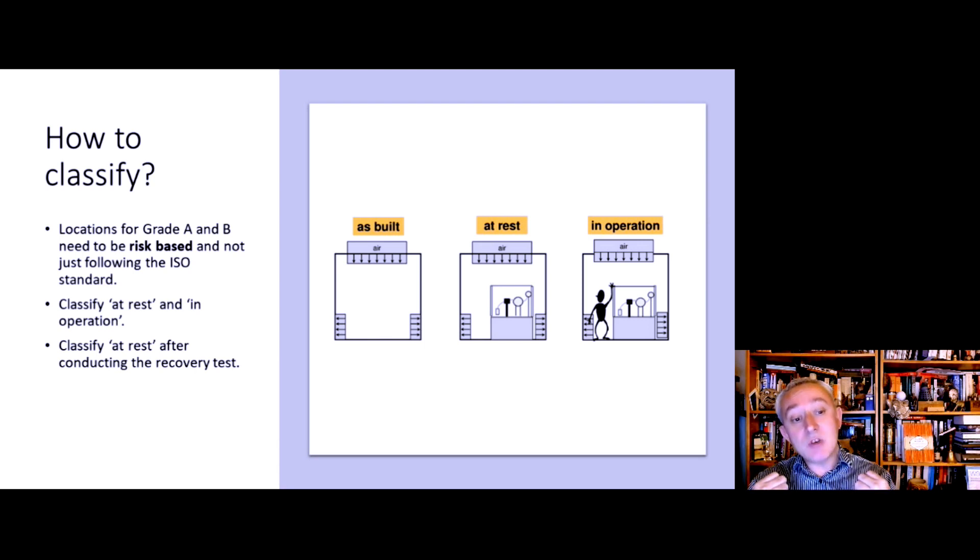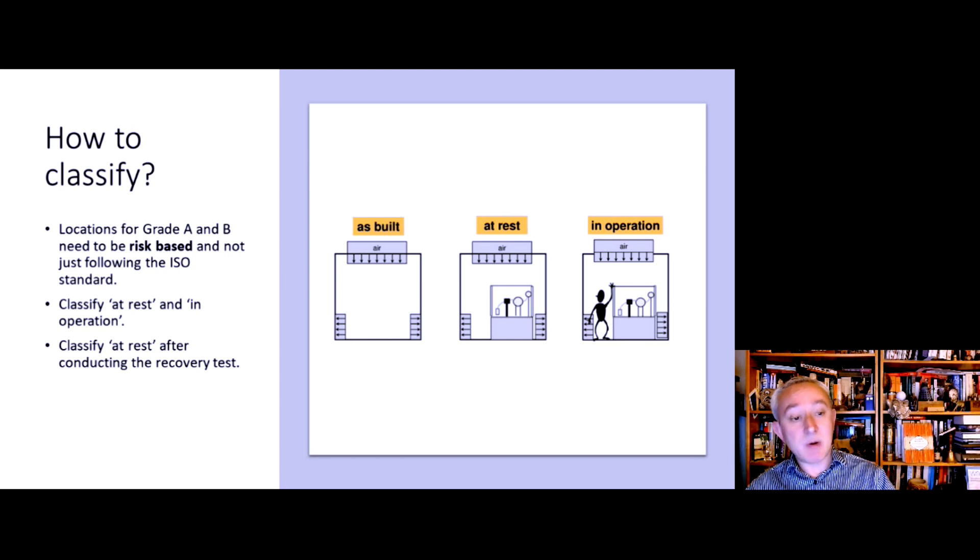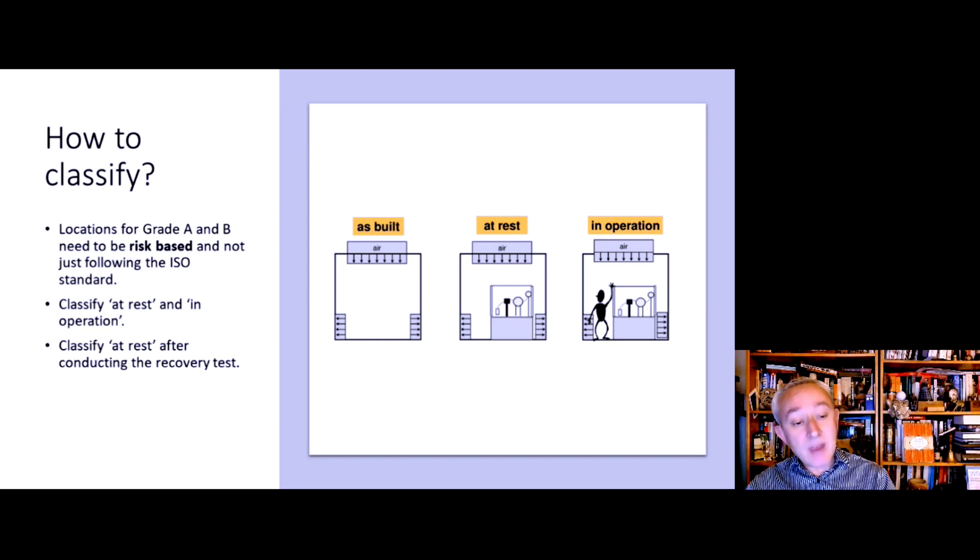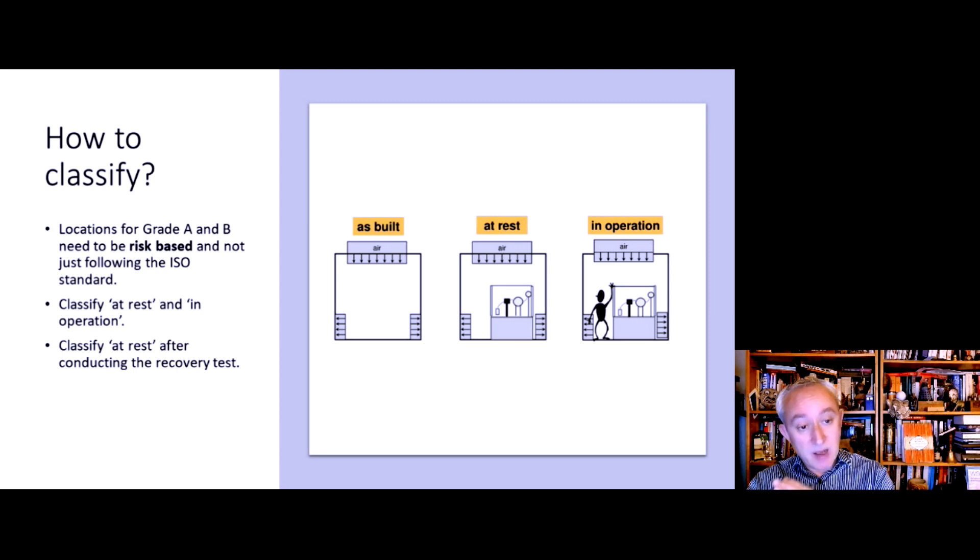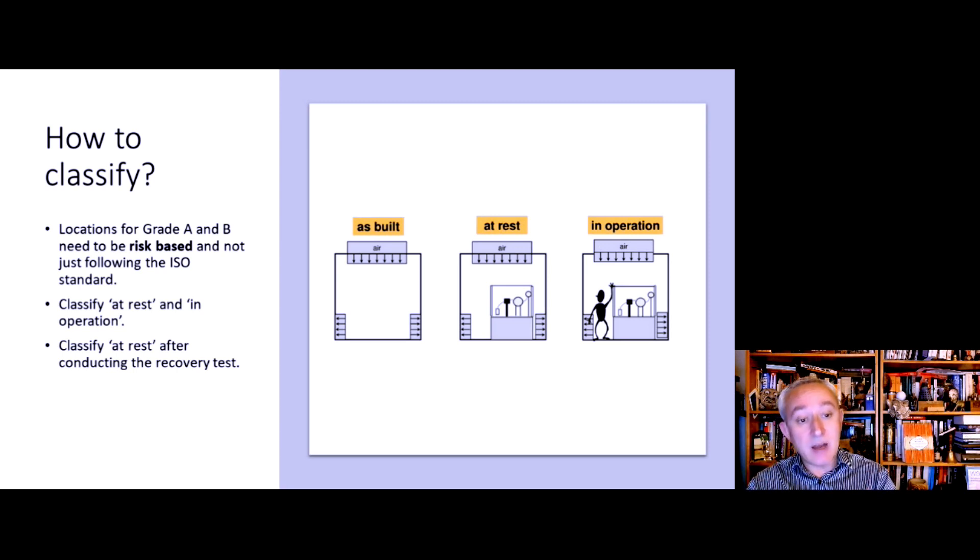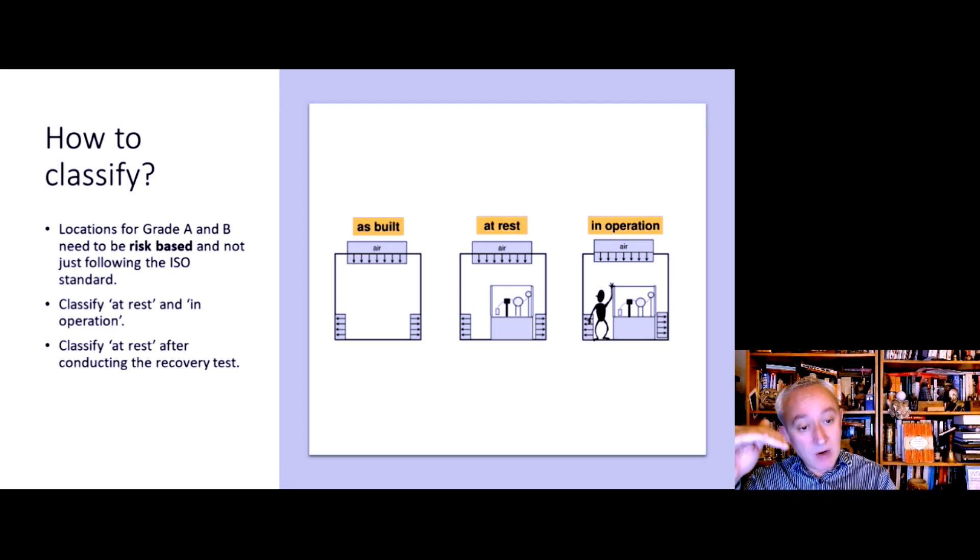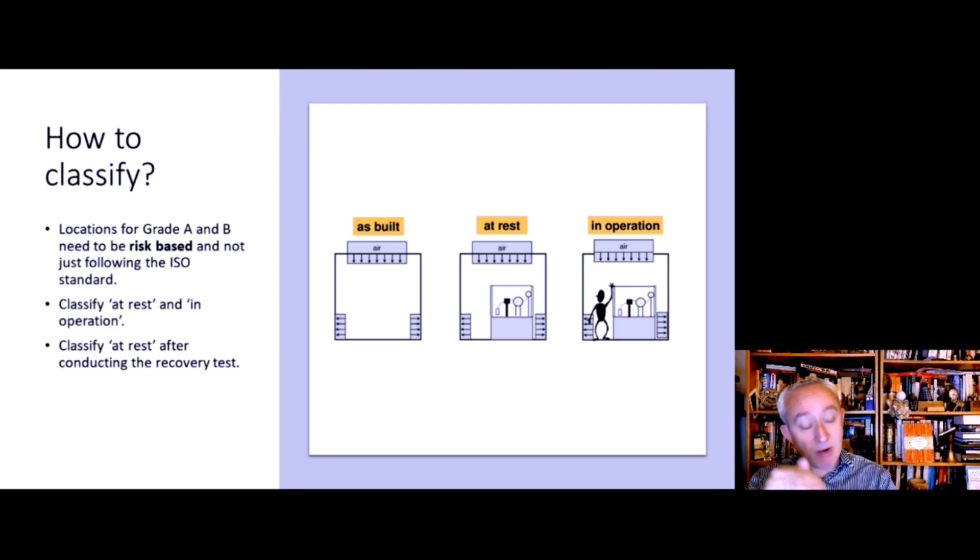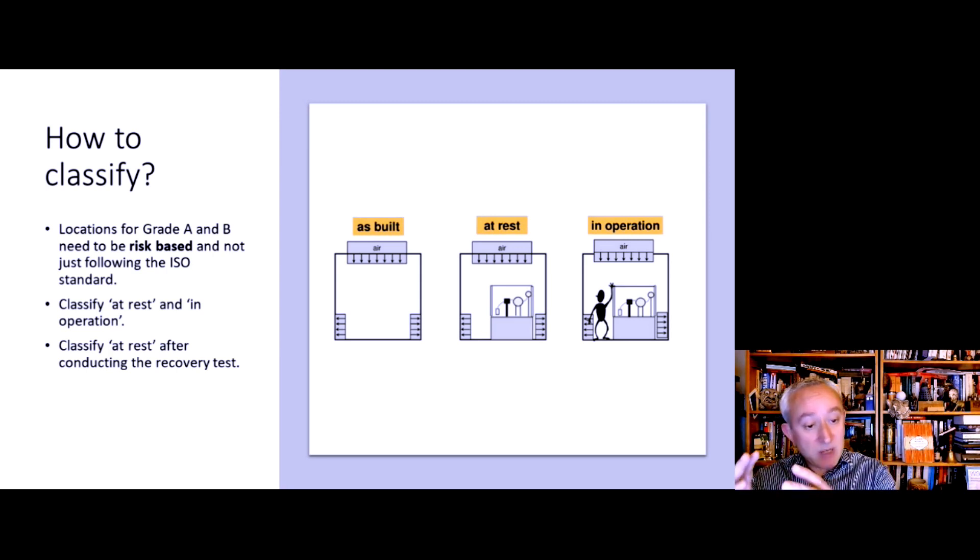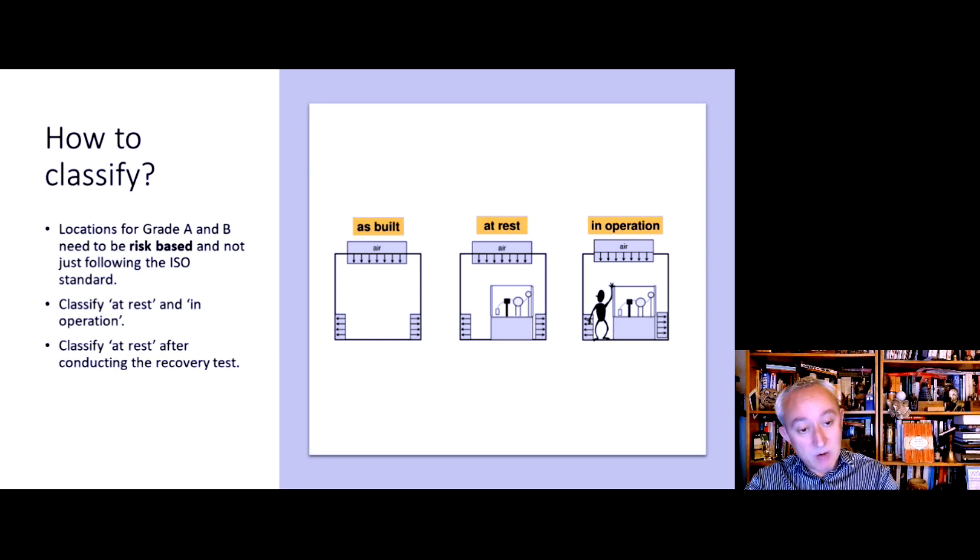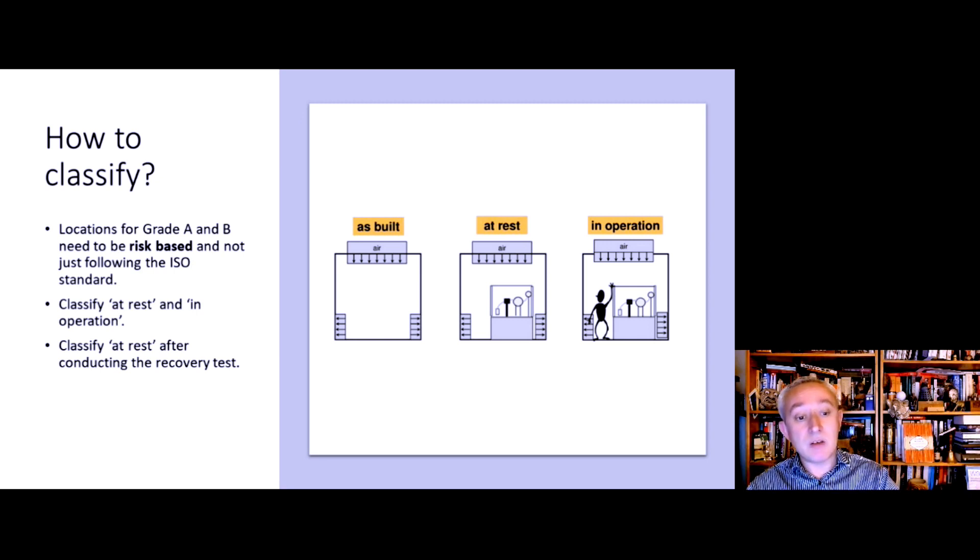For the at-rest state, there's this requirement to carry out a recovery test. That involves elevating the number of airborne particles to a level beyond the class limit for the room and tracking how long it takes to go down to at-rest. Often the procedure is you do the recovery test, then you do your at-rest qualification, and then move into in-operation qualification.